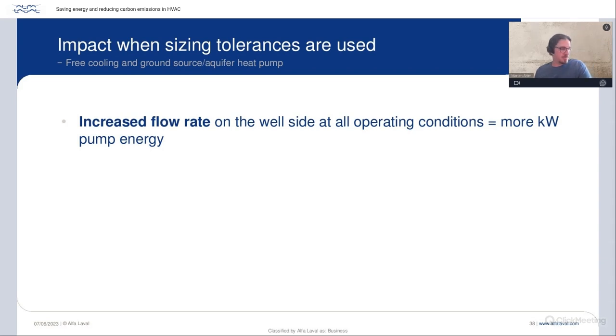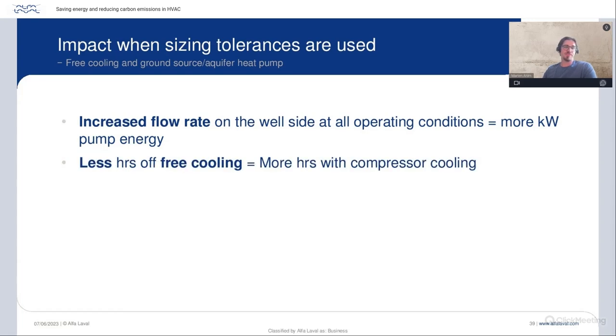So sometimes we get this response when we talk with customers about it. Well, they say, it's only at design conditions that you increase the pumping power, but that's not true. Of course, the heat exchanger which is underperforming at the design criteria will also be underperforming at part load. So for all different operating conditions of this installation, the unit will need a higher pump flow rate going through the heat exchanger, generating a higher pressure drop.